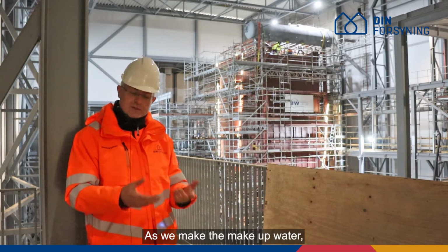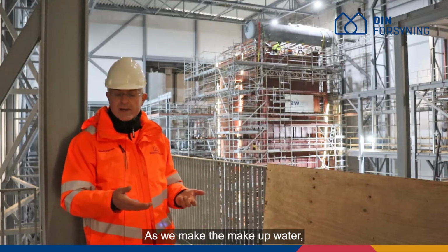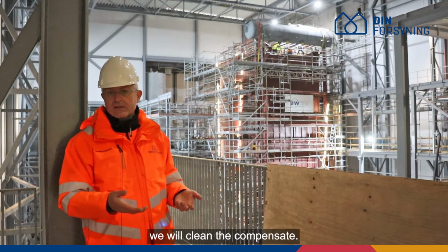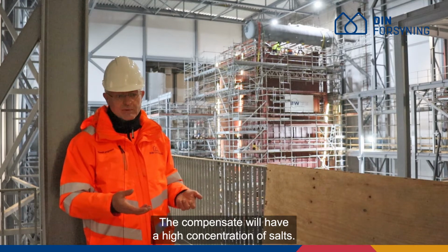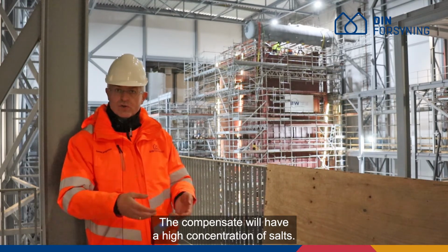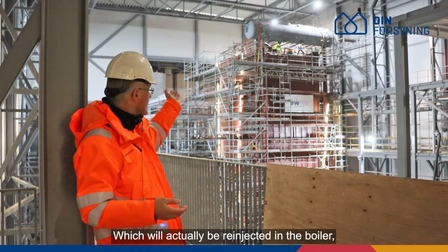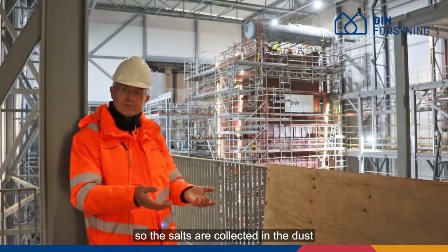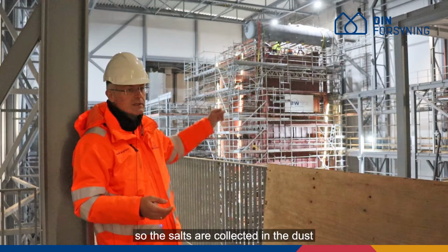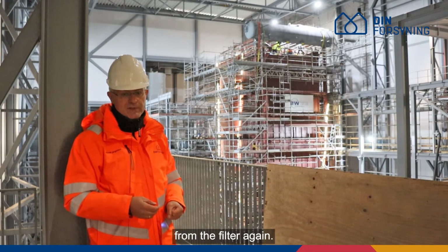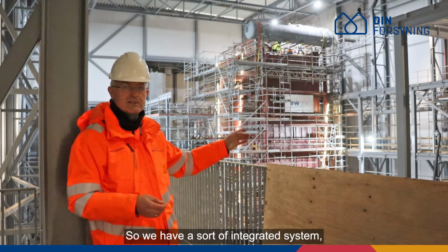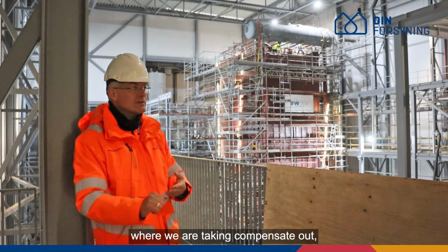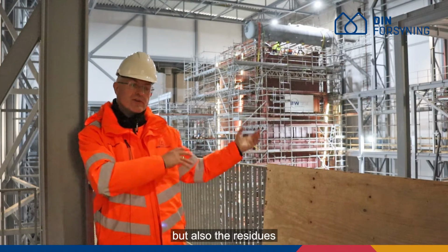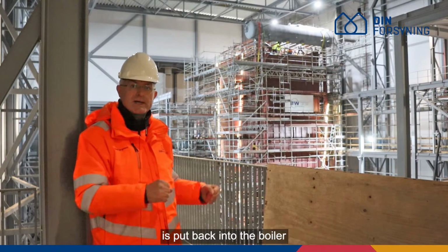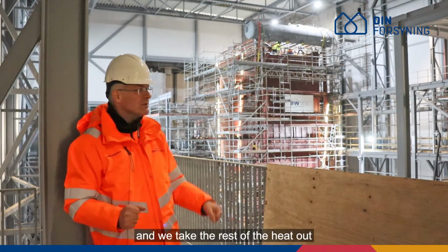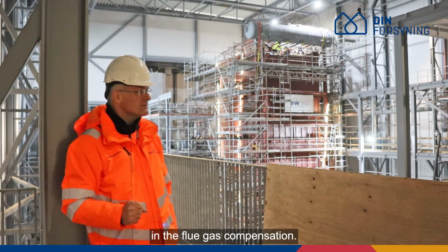As we make the condensate, we will clean it. The condensate will have a high concentration of salts, which will actually be re-injected in the boiler. So the salts are collected in the dust from the filter again. So we have a sort of integrated system where we are taking condensate out, but also the residues from the condensate cleaning are put back into the boiler and end up in this system. And we take the rest of the heat out in the flue gas condensation.